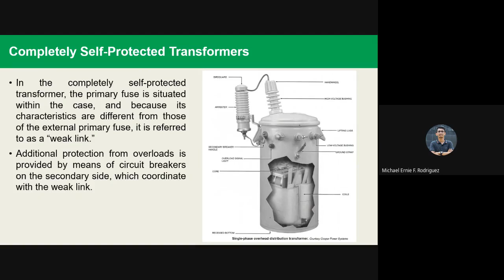So additional protection from overloads is provided by means of circuit breakers on the secondary side. So meron kang additional protection, which coordinate with the weak link. So naka-coordinate yan with your fuse. So dapat coordinated ang mga protections. And meron kang surge arrestor, tulad ng sa figure, that is mounted outside of the tank but it's connected to your primary winding. Ito, yung winding na nandito. So that is connected to your primary terminal.